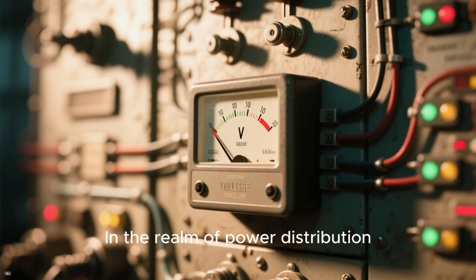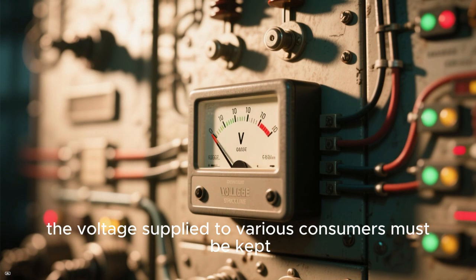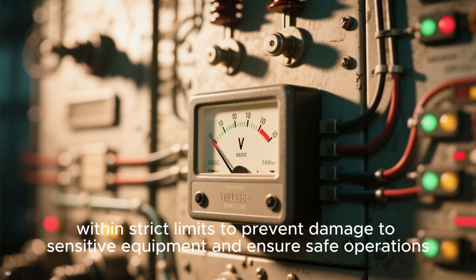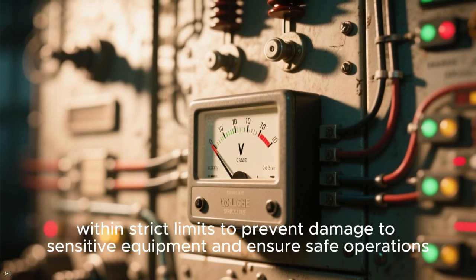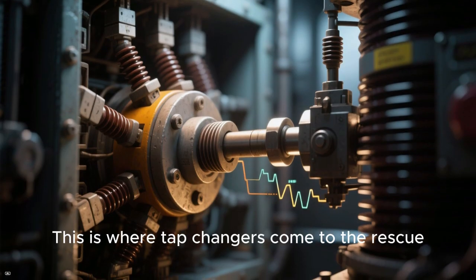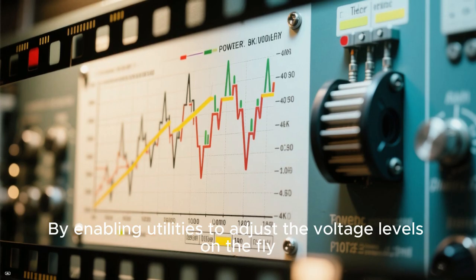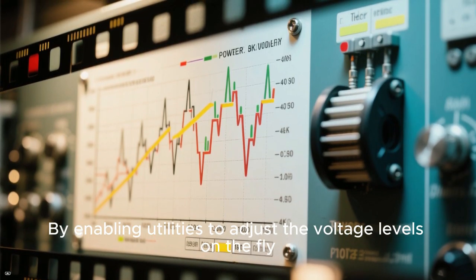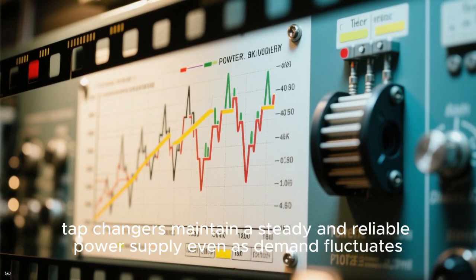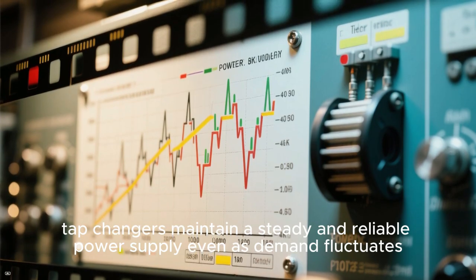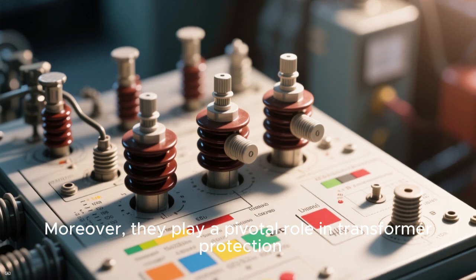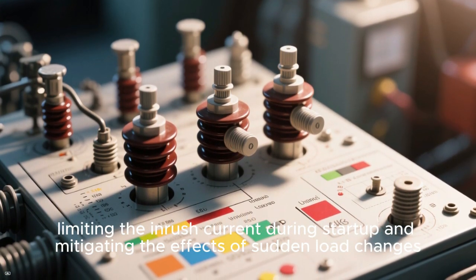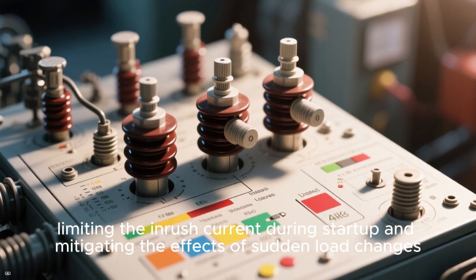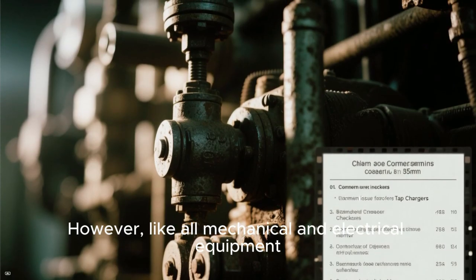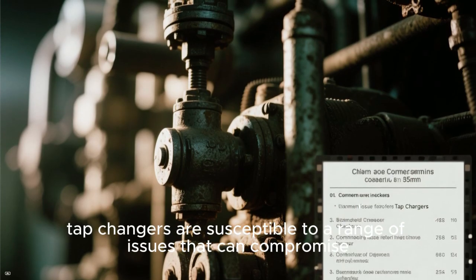In the realm of power distribution, the voltage supplied to various consumers must be kept within strict limits to prevent damage to sensitive equipment and ensure safe operations. This is where tap changers come to the rescue by enabling utilities to adjust the voltage levels on the fly. Tap changers maintain a steady and reliable power supply even as demand fluctuates. Moreover, they play a pivotal role in transformer protection, limiting the inrush current during startup and mitigating the effects of sudden load changes. However, like all mechanical and electrical equipment, tap changers are susceptible to a range of issues that can compromise their functionality and overall lifespan.